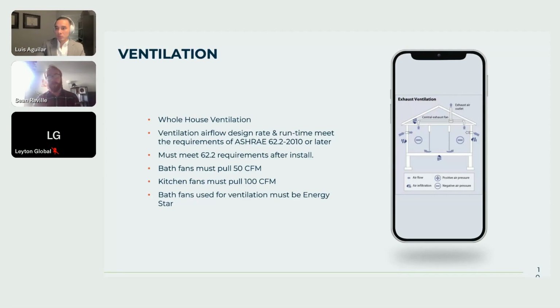So what that really means is if you're installing a 50 CFM bath fan, once you take into account line loss and that sort of thing, usually it's actually pulling about 38 CFM, in which case you would not meet that Energy Star requirement. So in that case, I always recommend you install an 80 CFM bath fan. Usually once you have the line loss in there, it's closer to 50 CFM, and then you can pass that 50 CFM requirement. There is a plus or minus 15% wiggle room depending on altitude and some of those, like if the air's thinner in certain areas. There are some exceptions for that, but those are generally the requirements. And if you are using a bath fan to meet 62.2 requirements, then that bath fan must be ENERGY STAR certified.